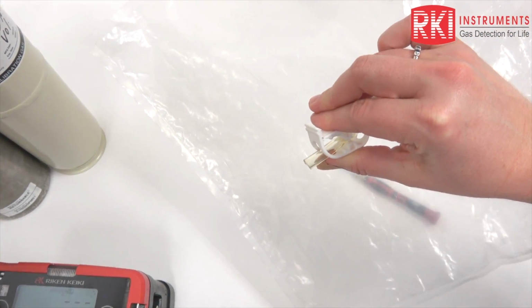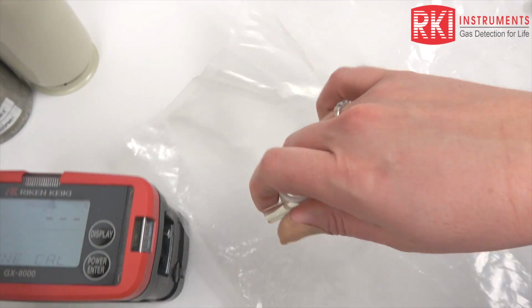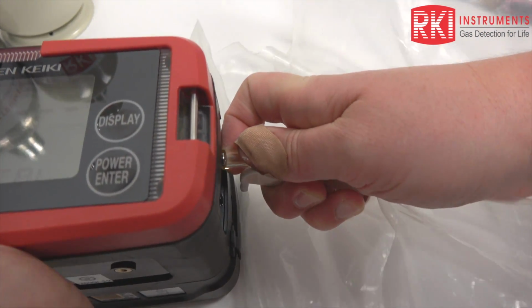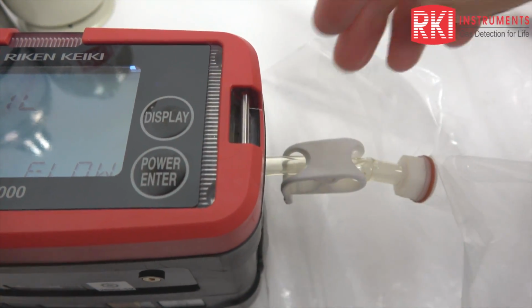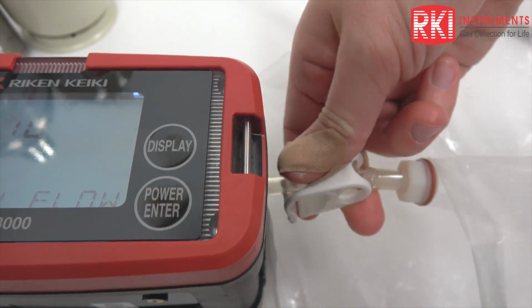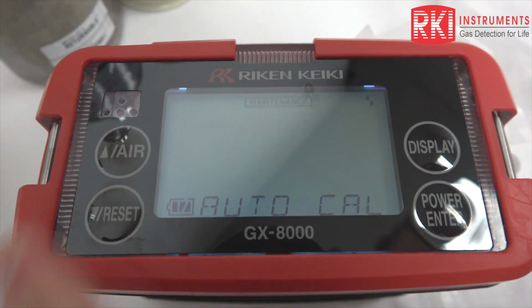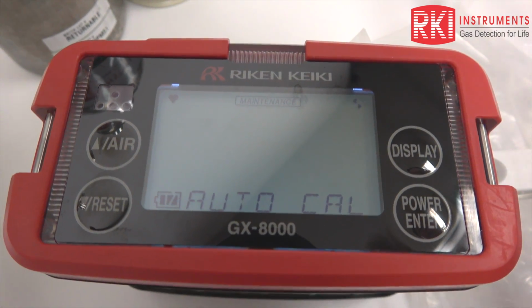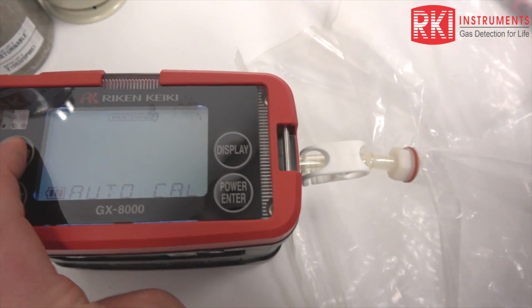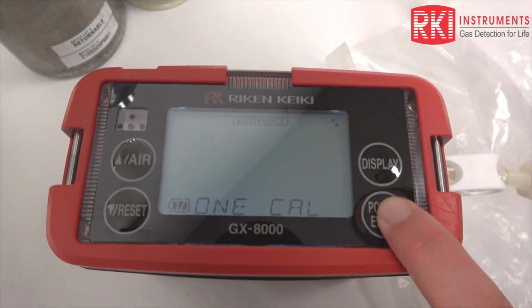So I have this, it's closed. I did the same procedure that you saw me do for the nitrogen. I'll put this on here. I got a flow fail. I'm going to go ahead and open the clamp and press reset. So now I'm drawing gas from my 4-gas mix gas bag. So I want to get back into 1 cal.